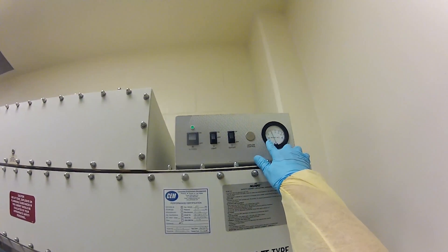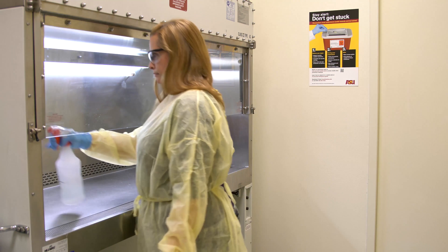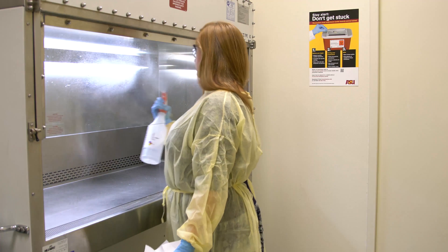On the sticker, note the pressure reference value and verify that the Magnehelic gauge reading is within 10%. Clean and disinfect all interior surfaces of the cabinet, including the inside of the sash.